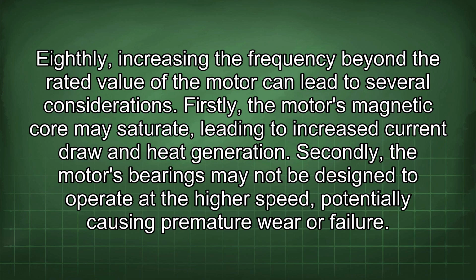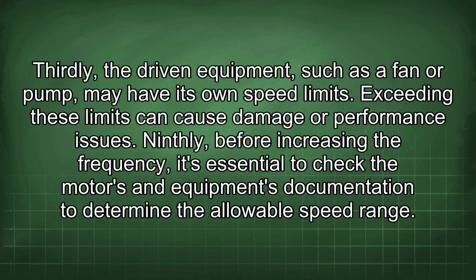Firstly, the motor's magnetic core may saturate, leading to increased current draw and heat generation. Secondly, the motor's bearings may not be designed to operate at the higher speed, potentially causing premature wear or failure. Thirdly, the driven equipment, such as a fan or pump, may have its own speed limits. Exceeding these limits can cause damage or performance issues.